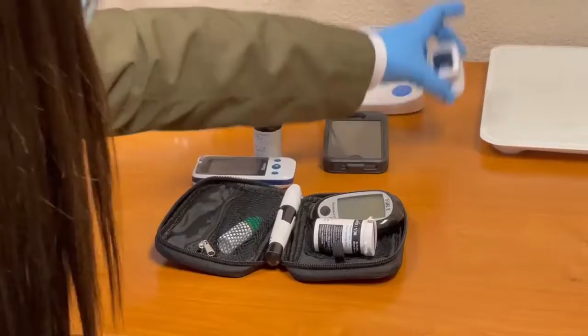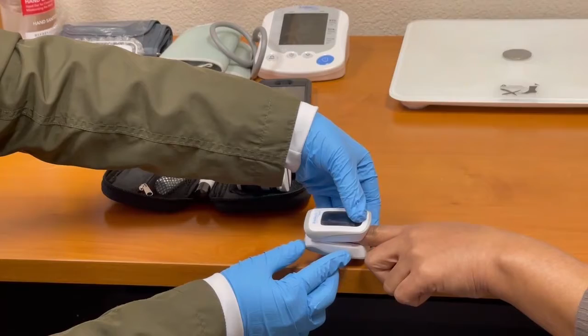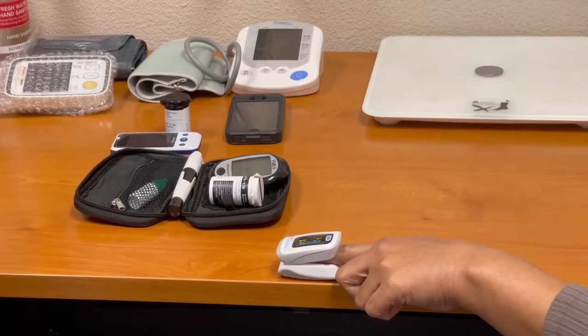Next is the pulse oximeter. This is used to measure your blood's oxygen level. Please insert your index finger. Just relax, and we press the blue button to start the reading. The hub will talk and say pulse oximeter connected. Once it talks, it means that the device started to take the reading. If it doesn't talk, it means it's not working. We will know when the reading is complete. The hub will say it's complete, and you can take your finger off the pulse oximeter.